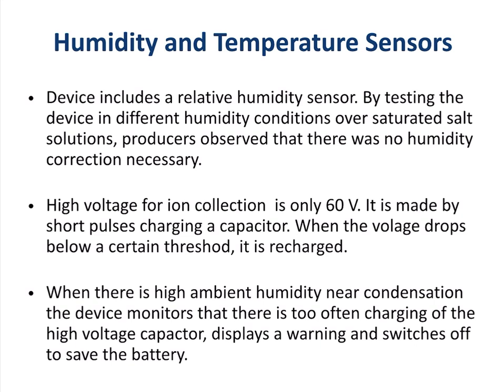High voltage for ion collection is only 60 volts. It is made by short pulses charging a capacitor. When the voltage drops below a certain threshold, it is recharged. When there is high ambient humidity near condensation, the device detects that the high voltage capacitor is being recharged too often, displays a warning and switches off to save the battery.